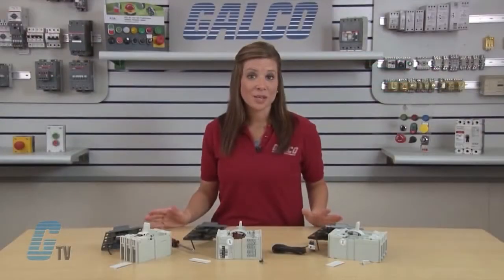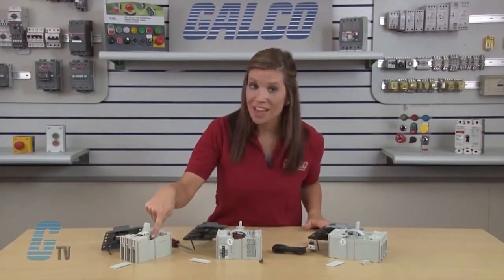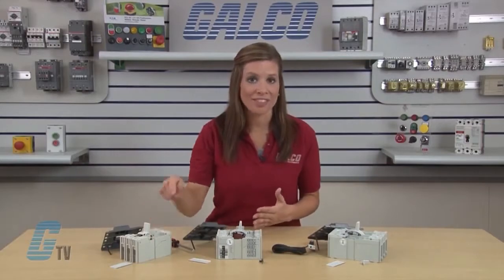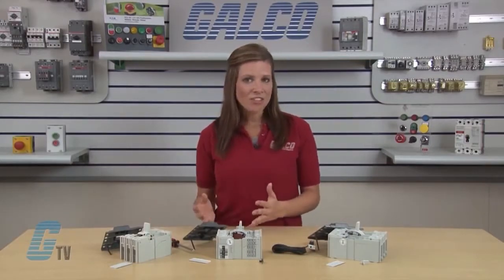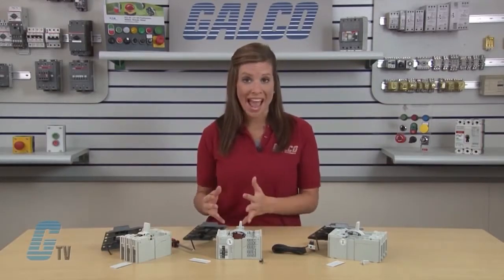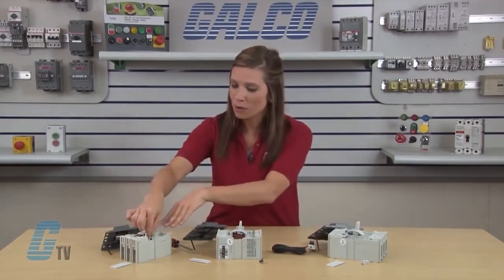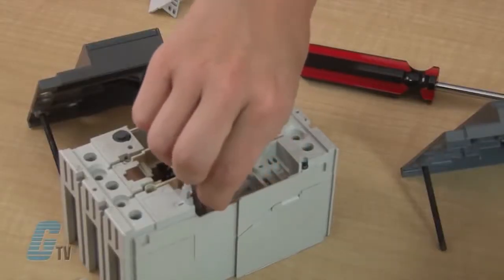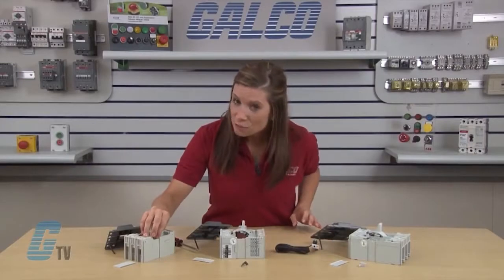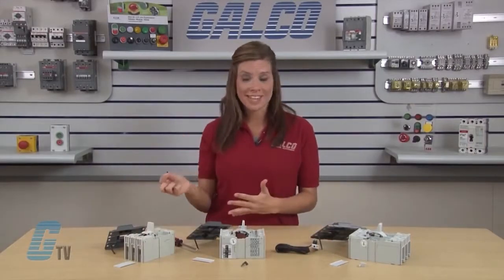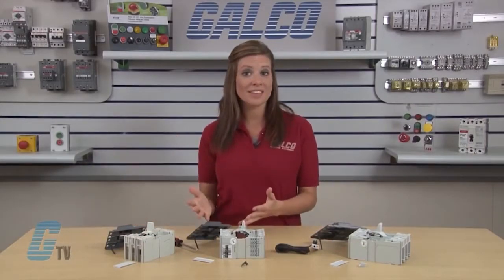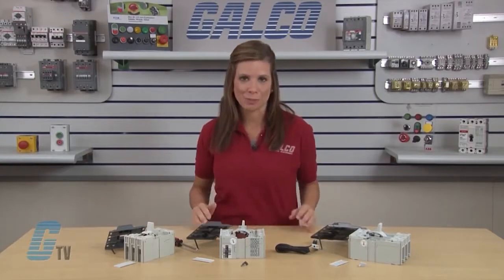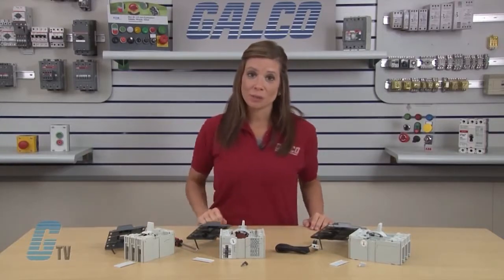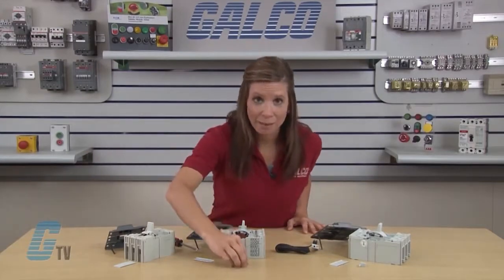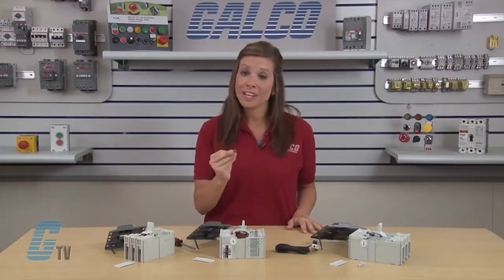Once installed, this installation feature will be removed by rocking the flag and mast back and forth until the parts separate at the narrowing. But first, I will insert the tapered tab into the slot at the back of the accessory port on the right side of the breaker. The adapter is seated properly when the flag portion of the extra plastic bottoms out on the side of the frame. Now the extra plastic, or flag and mast, can be rocked back and forth until it separates from the working part of the adapter. The extra plastic can now be removed and set aside for recycling, while the rest of the adapter can remain in the circuit breaker.